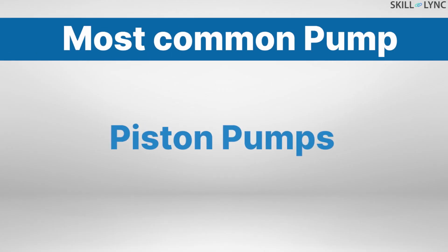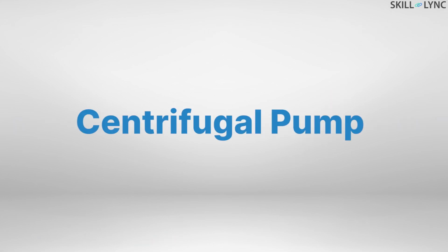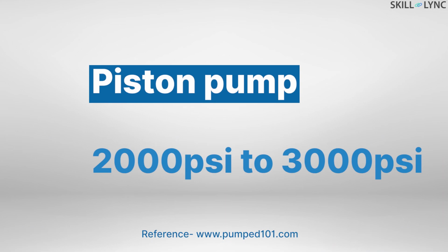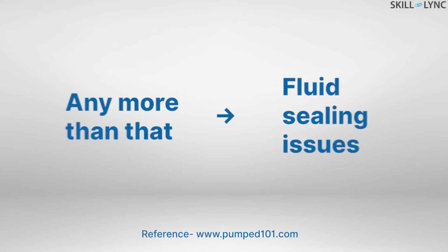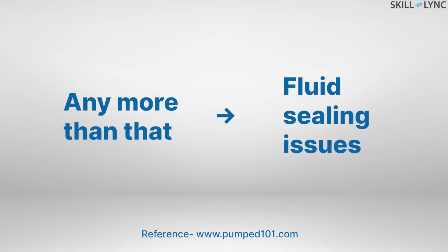The piston pumps were one of the most common pumps in the market. They lost their popularity to centrifugal pumps due to the development of high-speed drivers. Piston pumps are only used for low to moderate pressures of about 2000 to 3000 psi. Any higher than that, complications in sealing would arise.